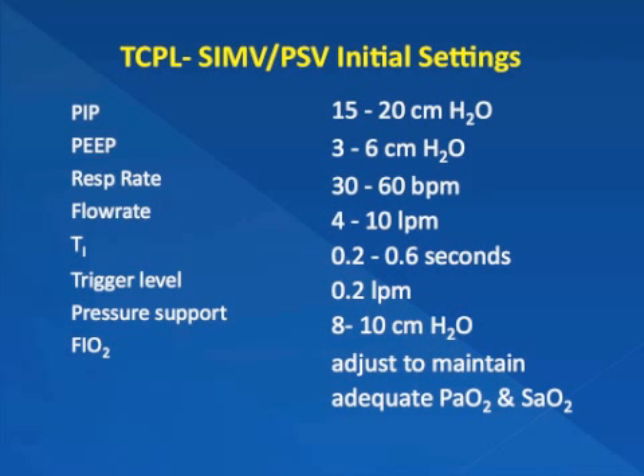But the key point in just giving you these settings, whether it's time cycle pressure limited, whether it's pressure control, whatever type of ventilation that you're using, is making sure that you're reassessing your initial starting settings. Looking at those things in terms of your PIP, looking at your chest excursion, looking at your exhale tidal volume, looking at your pressure volume loop to make sure that you have the proper initial settings for that particular baby.